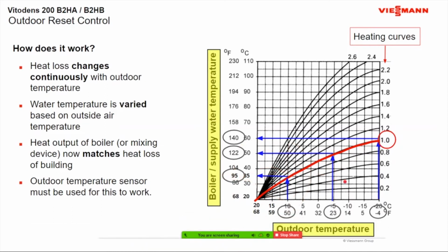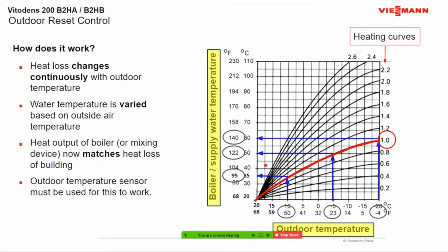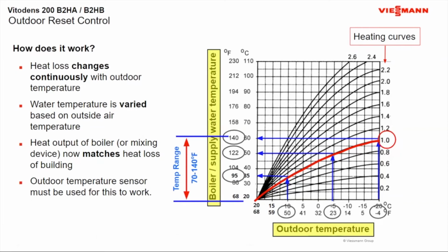My heating curve set in my house is about 0.5 for some of my radiant. So if you follow that over, you can kind of see what temperatures I am using to heat my house. Just remember, I am doing constant circulation through radiant. For this example, our temperature ranges are anywhere from 70 to 140 degree water temperature. So now you can see how you can get that savings by modulating through your heating curve. But just make sure you get it right on the coldest day of the year, whatever your coldest day of the year is. Make sure you set it to what their comfort needs are.